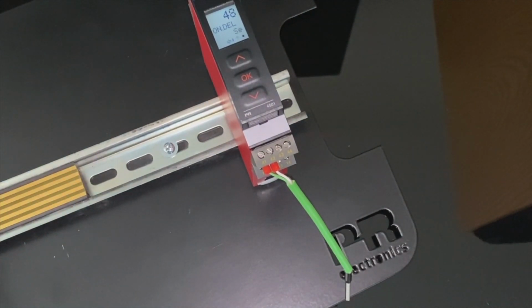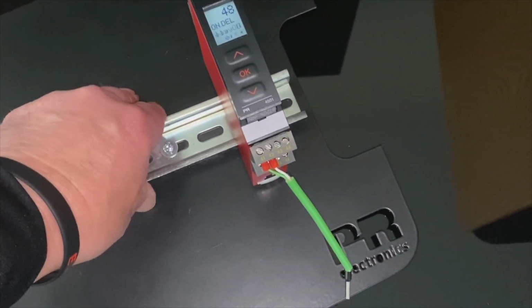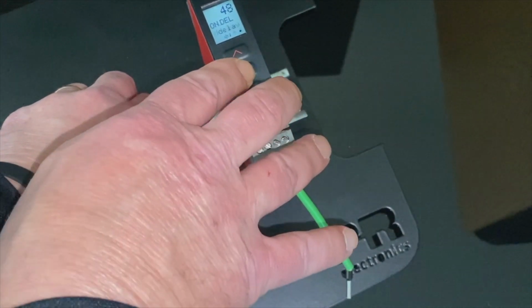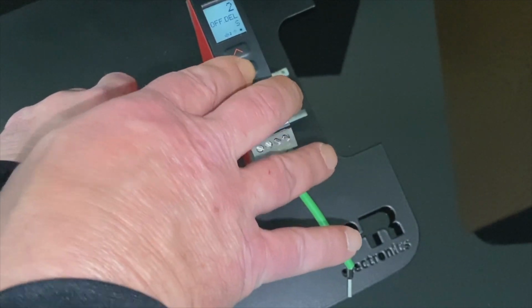Generally, where this would be used, a good example might be you're filling a tank, you're measuring level, and initially when you fill a tank, you're going to have some turbulence. So you may want to add a delay to your relay to make sure that you've really attained that value and you don't have chatter. Both on and off delays.